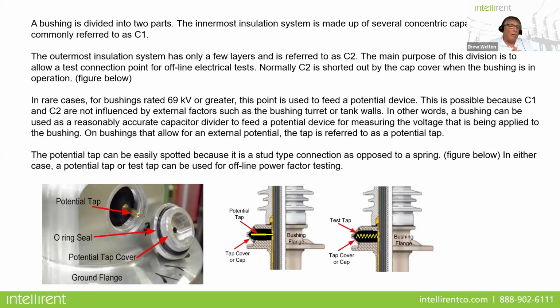Very important. Now, in rare cases, for bushings rated 69 kV or greater, this point is used to feed a potential device. It's possible because C1 and C2 are not influenced by external factors such as bushing turret or tank walls. In other words, a bushing can be used as a reasonably accurate capacitor divider to feed a potential device for measuring the voltage being applied to the bushings. So on bushings that allow for external potential, the tap is referred to as a potential tap.